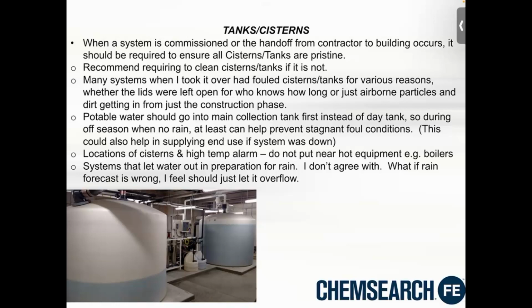One idea: I feel potable water should go into the main collection tank first instead of the day tank. During the summer months when there's no rain and that tank is dry, but it has maybe half a foot of water, at least we can prevent stagnant, foul conditions. Having the potable water go into the main collection tank first could also help supply the end use if the system was down.